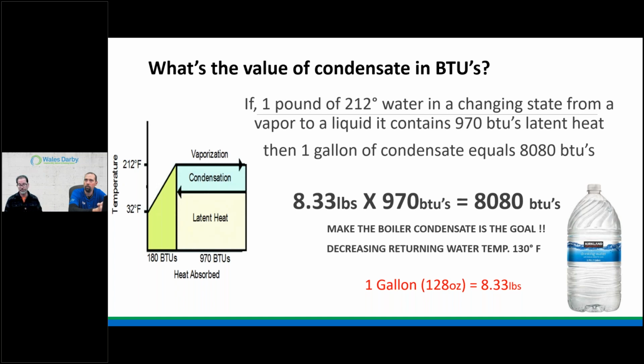And if you were to capture it in a bucket, let's say, just have it drip into a 5-gallon bucket, well, 1 gallon is 8.33 pounds, right? And therefore, times 970 BTUs. When I'm having that change of state from a vapor to a liquid, it releases energy, and there's that 970 BTUs. So having a pound of this condensate times 970, that's just about 8,000 BTUs worth that would be reclaimed. It's in our pocket again. It's not out in the atmosphere. So just take that to heart and think what that can do for your fuel consumption, right? And for your customers. And if that's their end-all goal, or you need to achieve certain efficiencies, just buying the appliance doesn't get it done. You need to set up the system.